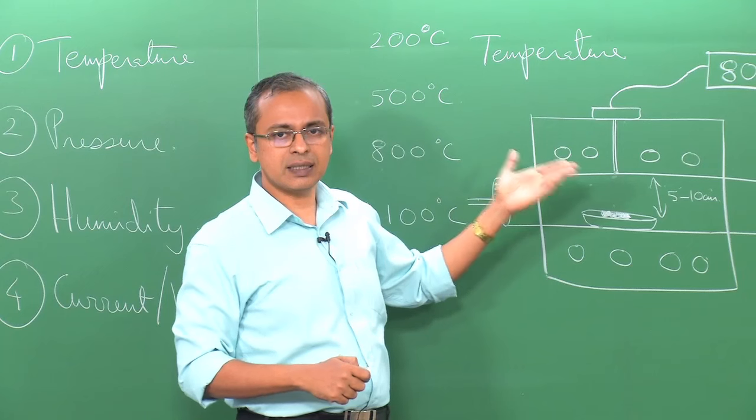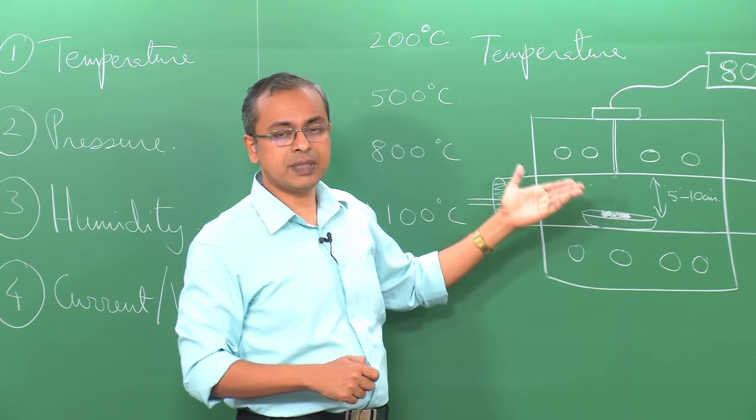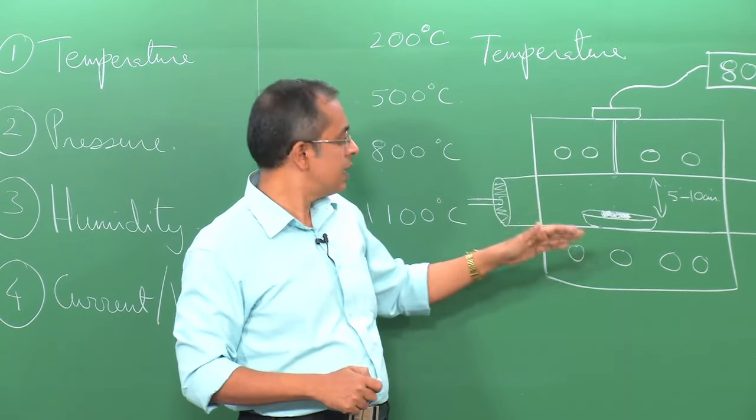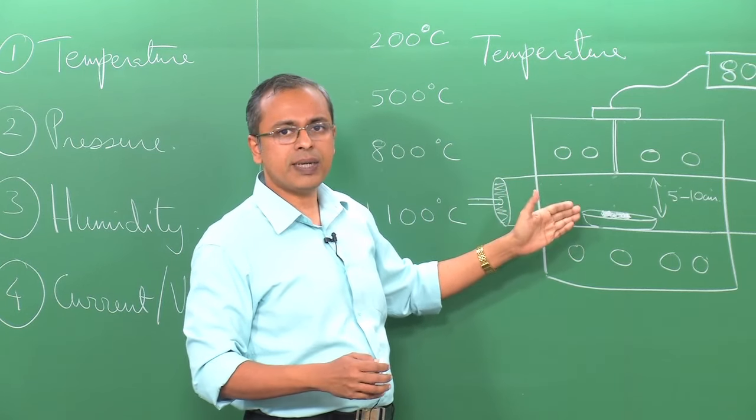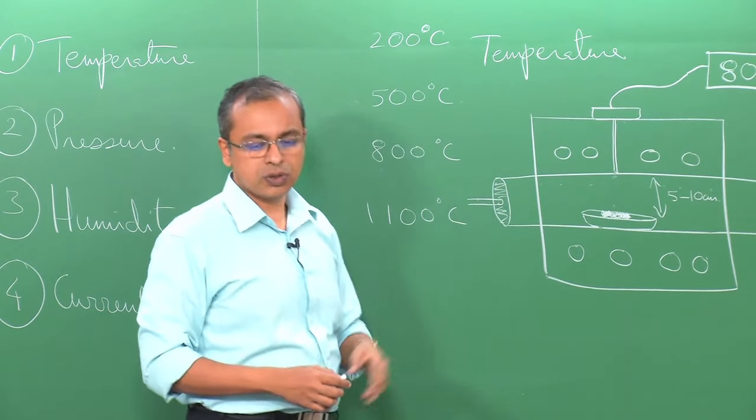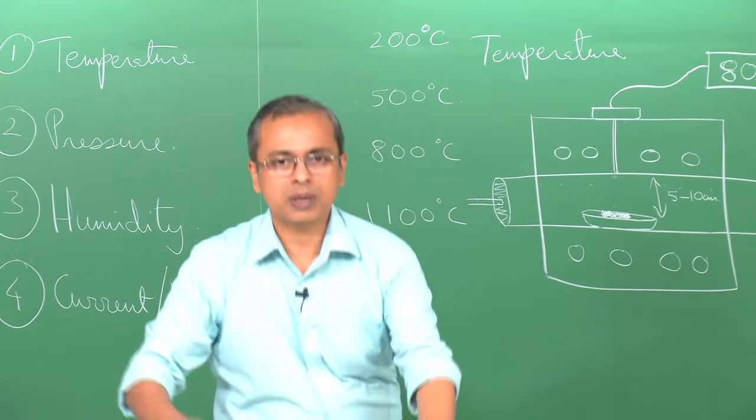If you know that this is something you have to address, something you have to carefully note down, then you can easily address it. The simplest way to address this is to add another thermocouple. So, for example, this is a thermocouple, right.